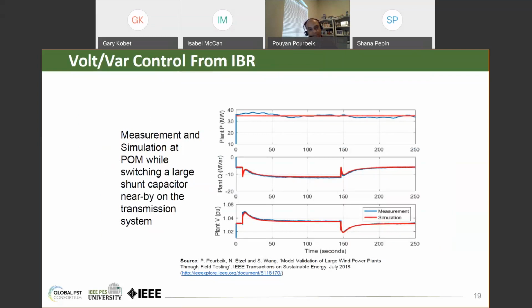And the top plot is the plant's total megawatts at the POI. This is a wind plant. The plot in the middle is the reactive power at the point of interconnection, and the plot at the bottom is the voltage at the point of interconnection. And the event here was a large shunt capacitor on the grid being switched, and you can see that when it was first switched at the beginning, you had a sudden jump up in the voltage at the POI.